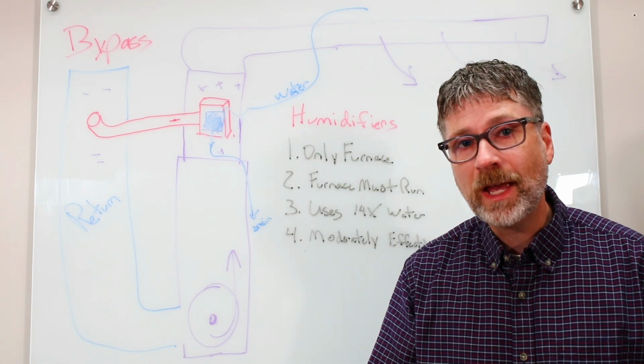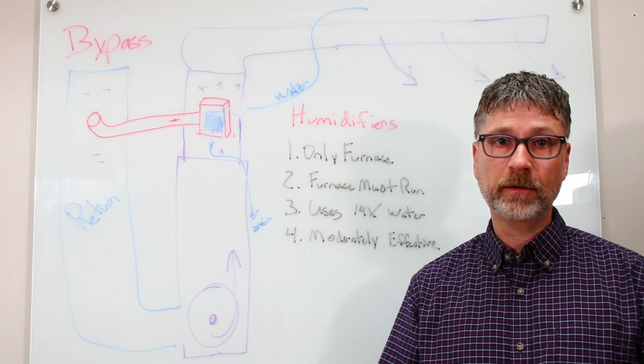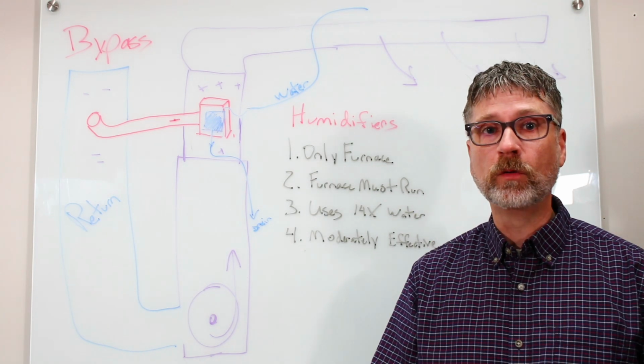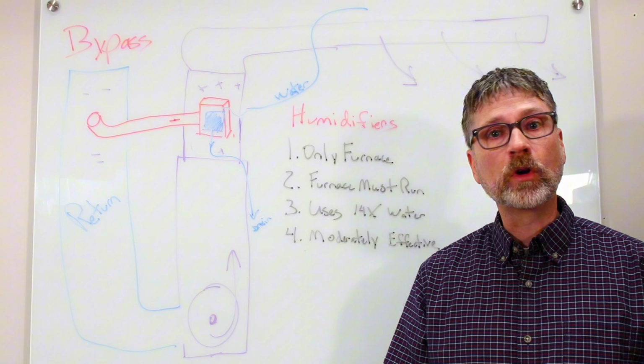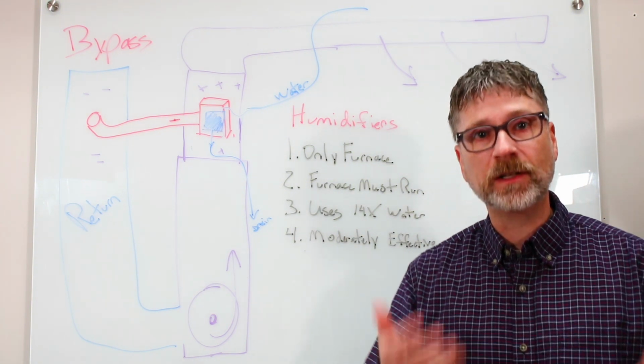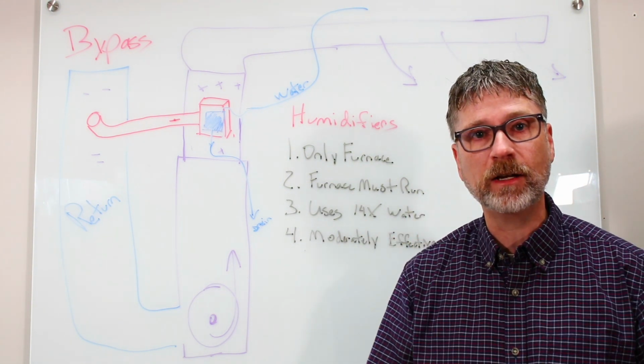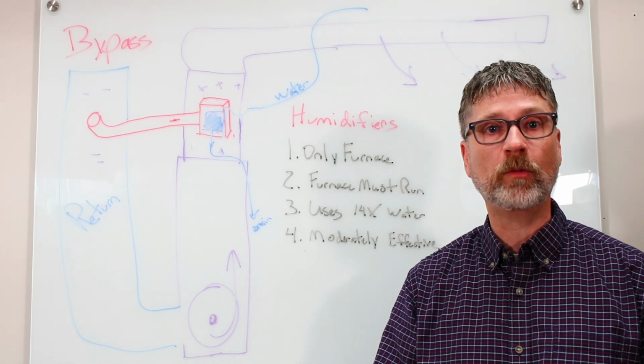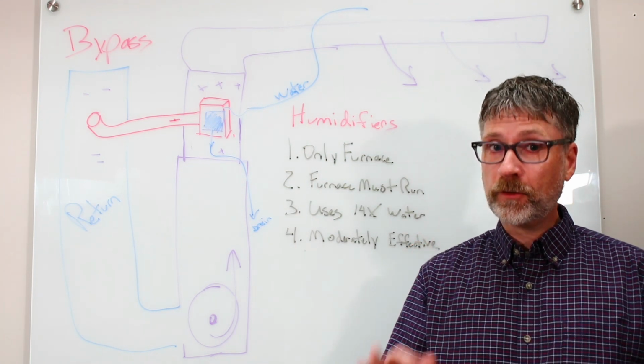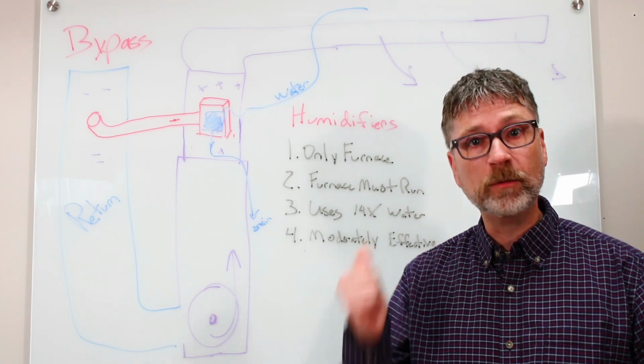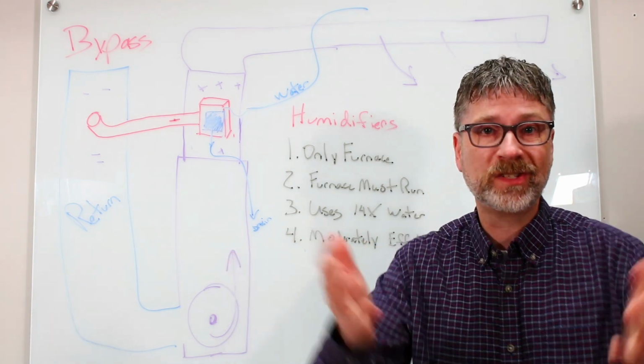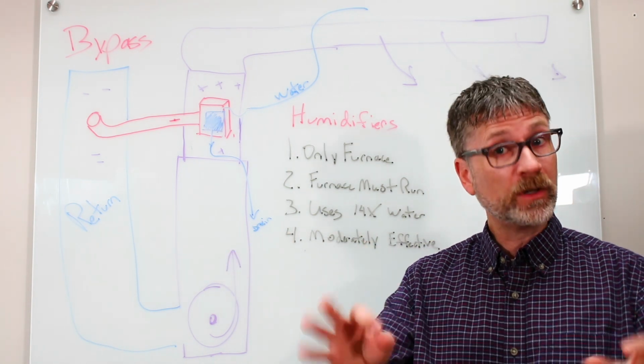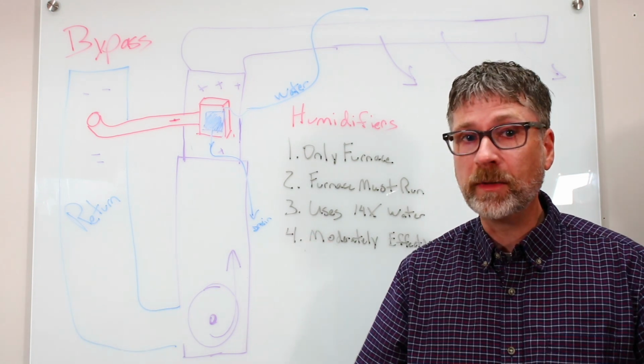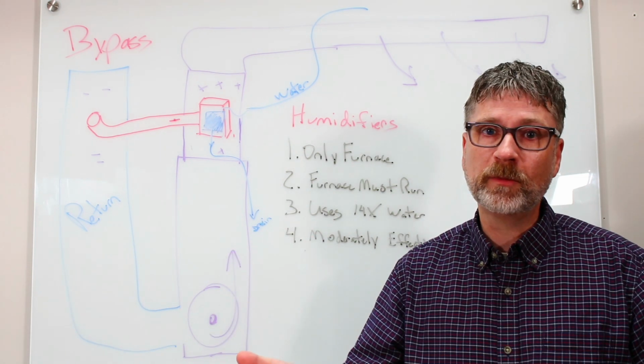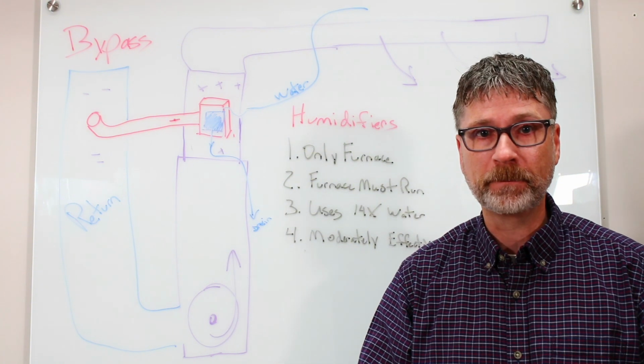So there are some limitations with the bypass humidifier. First off, it is a furnace-only sort of tool. Heat pumps don't work well with bypass humidifiers, as the air temperatures they produce are just not high enough to do a good job evaporating that water. Next, the furnace has got to run for the humidifier to work. When it's 60 degrees out, for example, your furnace isn't running much, and your air could be really dry, but your bypass humidifier is not running, so it stays dry.